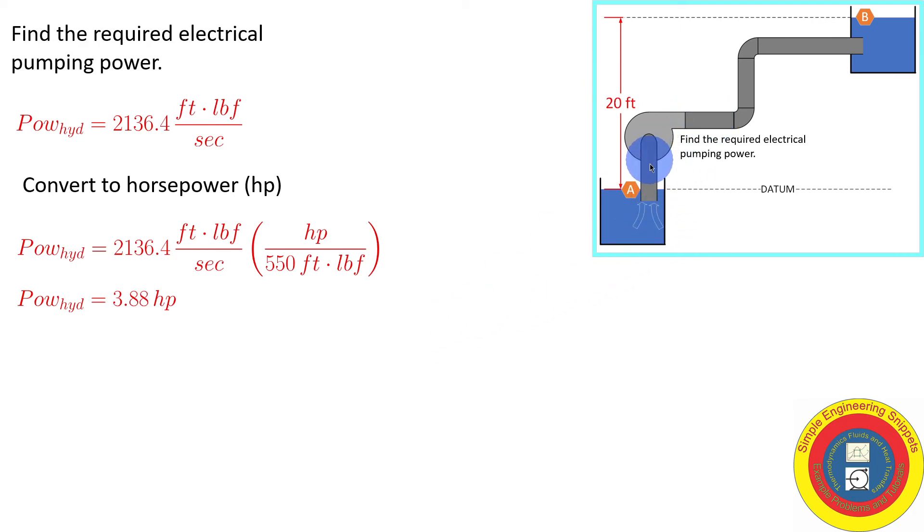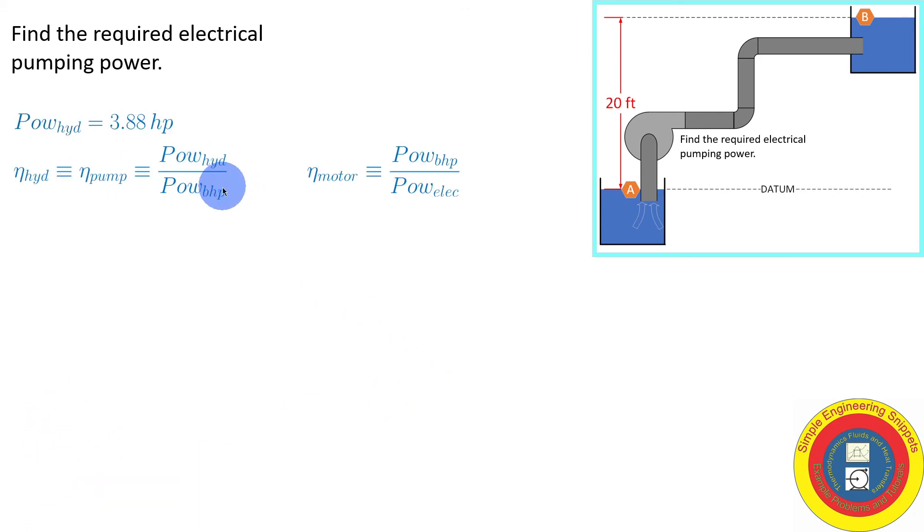We want to find the electrical power that's being supplied to the motor that is driving the pump. We're going to make use of the efficiencies that are provided. The hydraulic efficiency and the pump efficiency are one and the same, defined as the hydraulic power divided by the brake horsepower. That's the mechanical power coming out of the shaft of the motor. The motor efficiency is the brake horsepower divided by the electrical power, which is what we're looking for. Luckily, these two efficiencies are known.